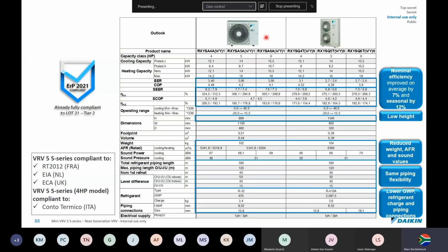When comparing the 410 system with the R32 system, we've just done a few highlights here. The nominal efficiency is improved by 7%. That's EER, and your seasonal efficiency is 12% better. They also have a lower height. They're smaller units because they're using R32. Reduced weight. The AFR, which to be honest with you, I do not know what that means. And your sound values. They have the same flexible piping configurations.